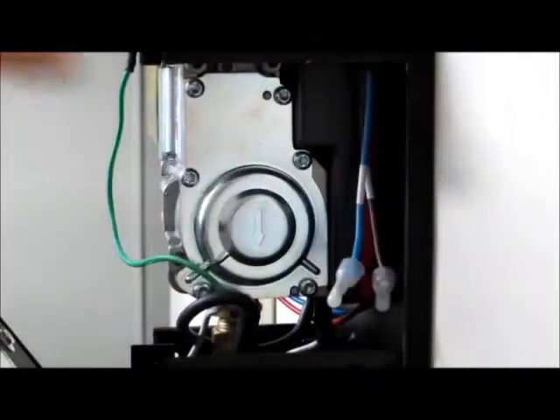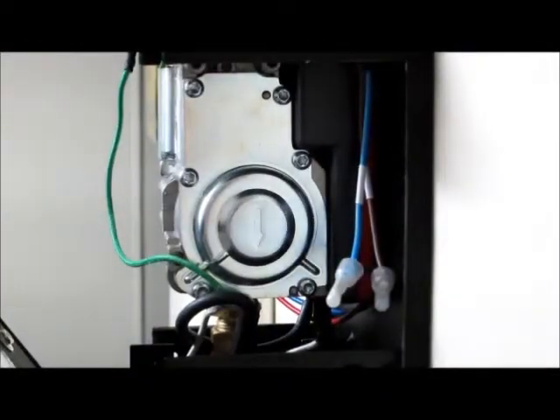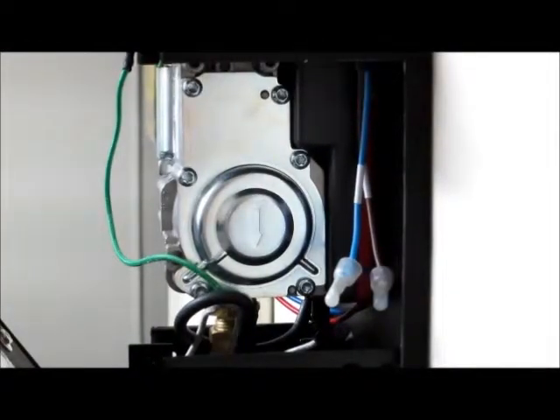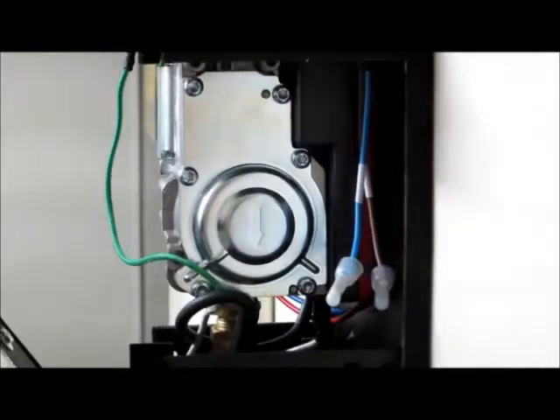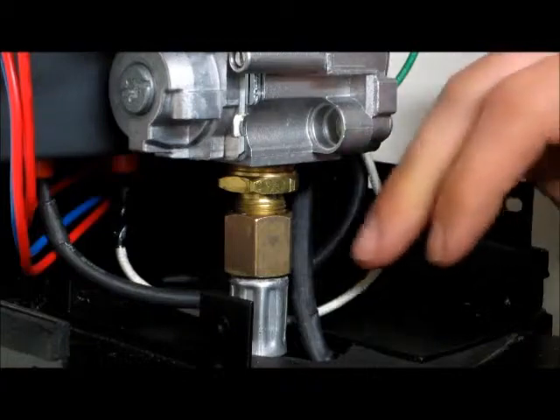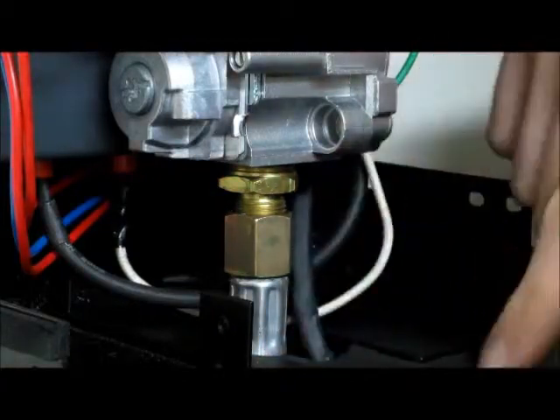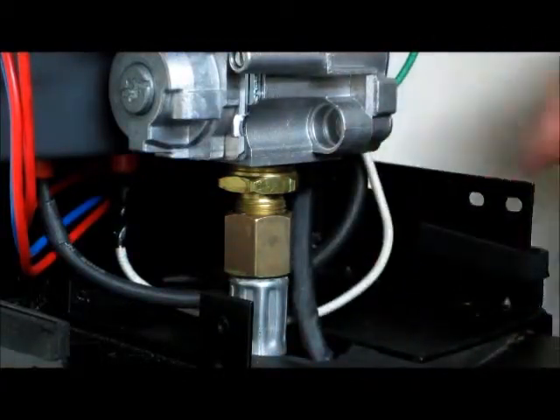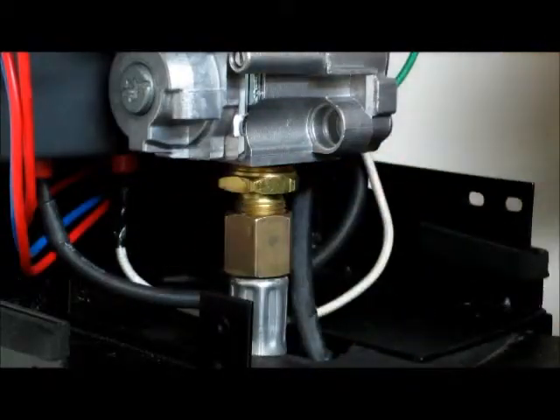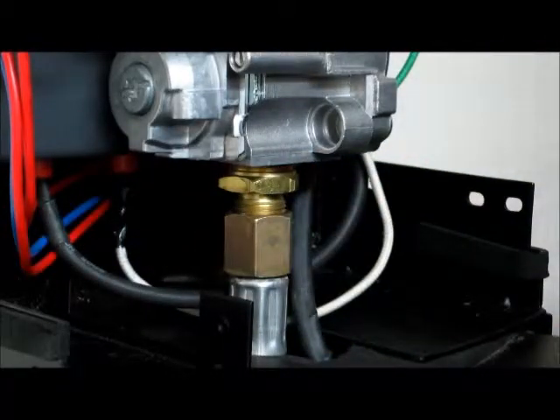If the heater is sparking at the ignition point correctly and still failing to light when gas supply is turned on, firstly inspect the gas valve to see that the gas flow indicator is pointing down, indicating gas will flow in the correct direction to the unit. Next, inspect the short flexible gas hose between the control valve and the heater. If the hose is crushed or kinked, reposition to rectify, or if damaged, ensure your dealer is contacted for a replacement hose.